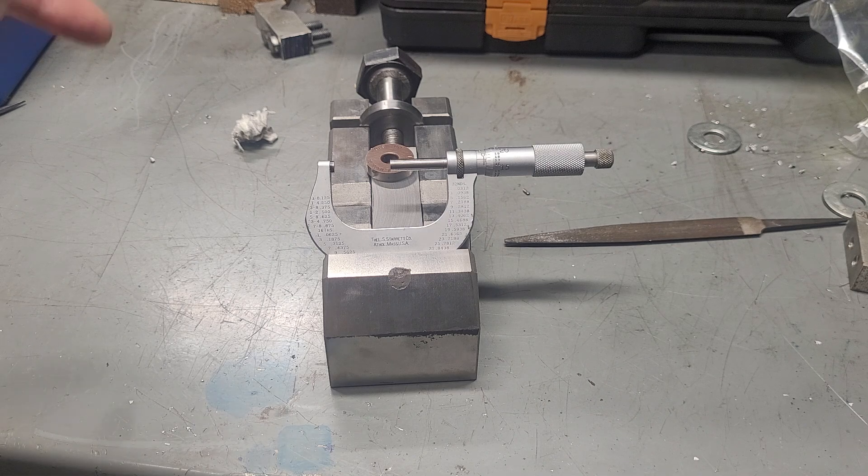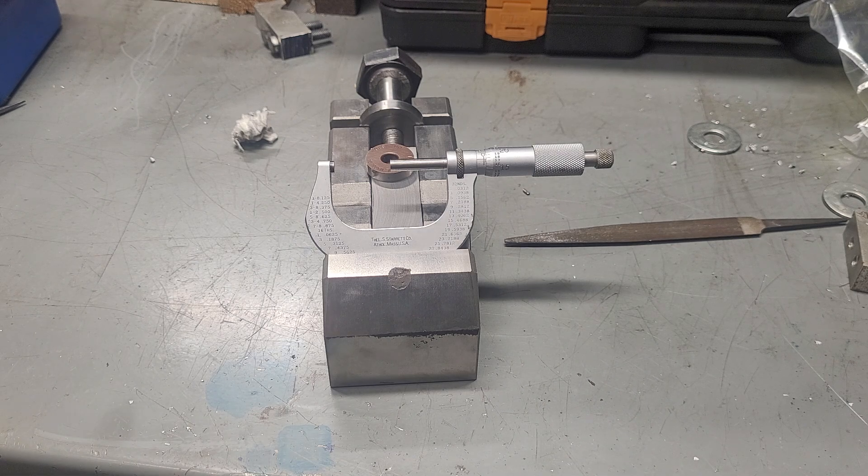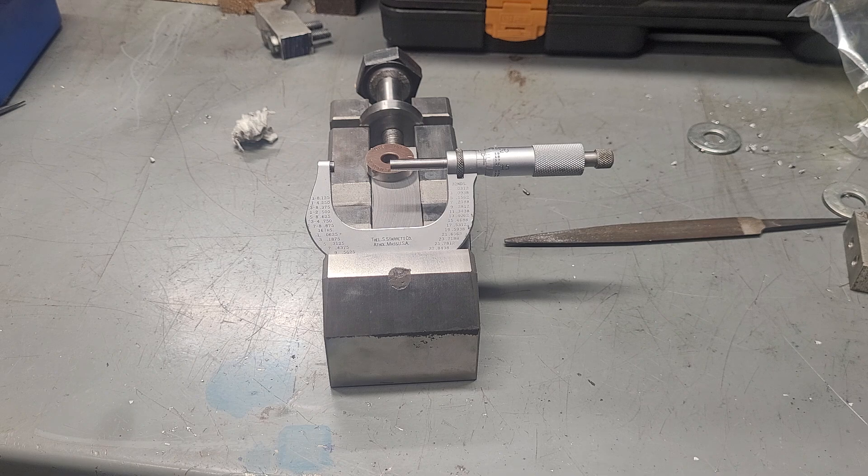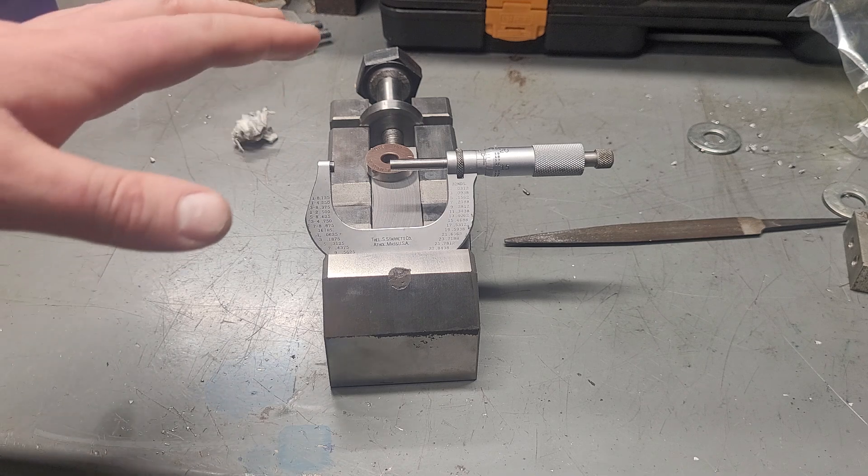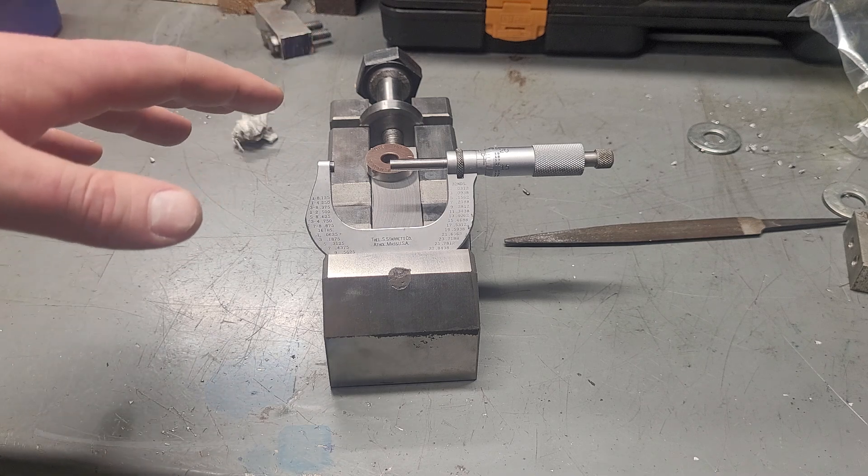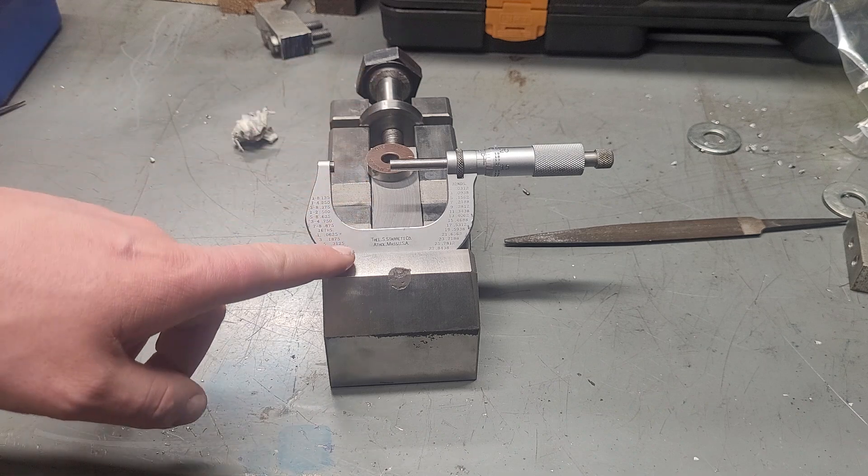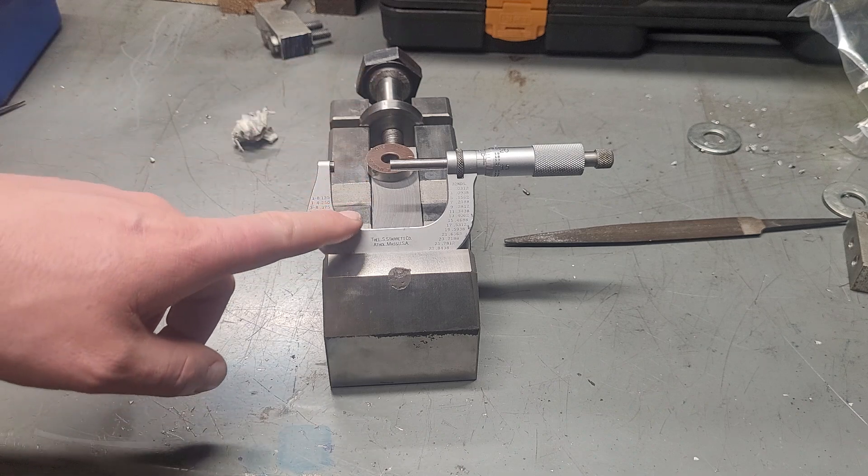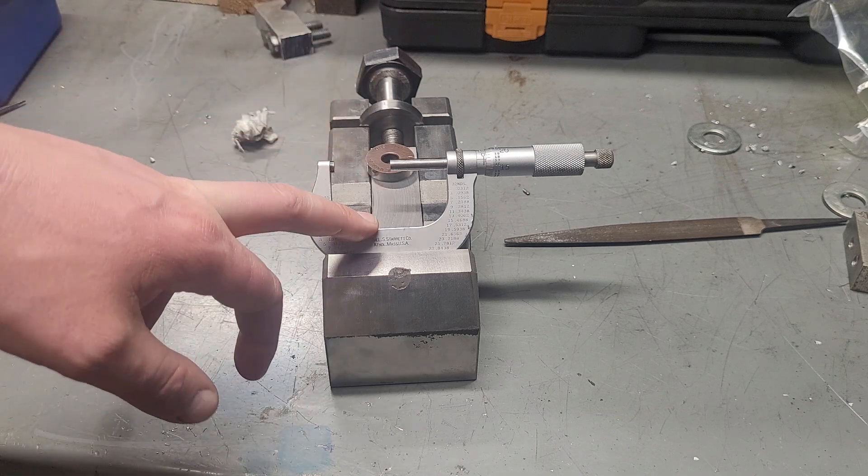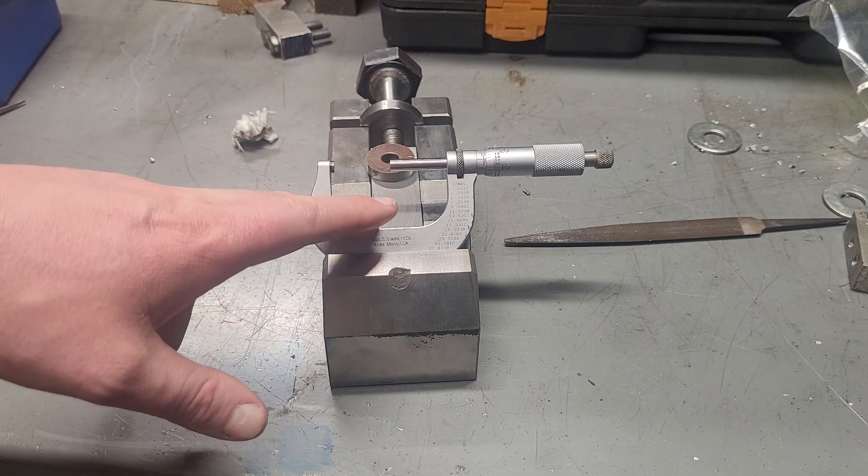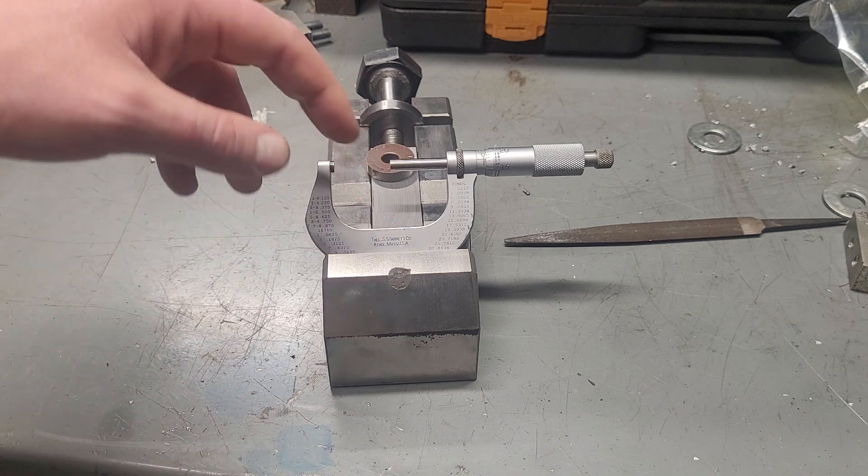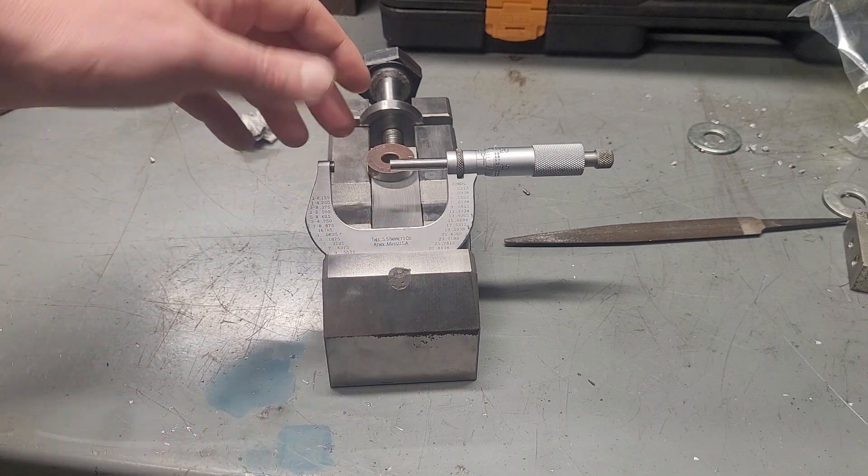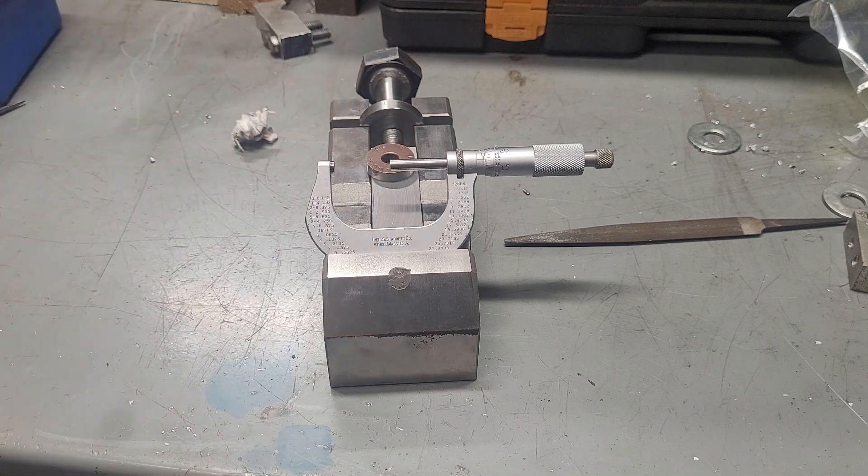These are lapped, I believe, to within one micron, give or take. The theory is this should be 10 times more precise than the instrument it's used to calibrate. This is only accurate to within one ten thousandths of an inch. So this needs to be an order of magnitude more precise.